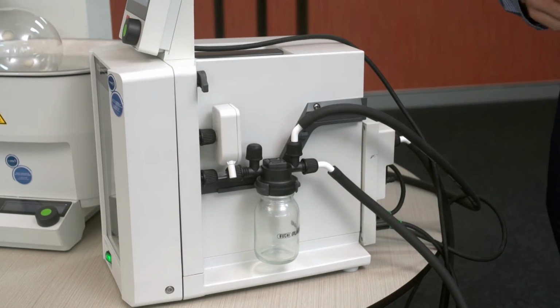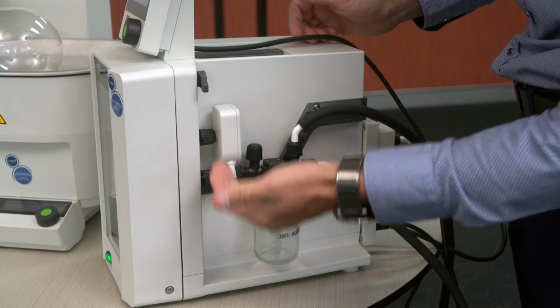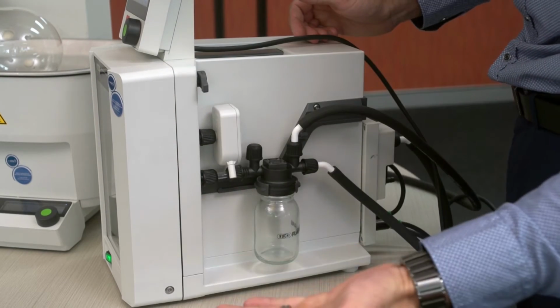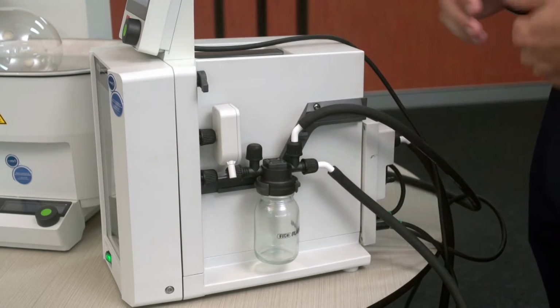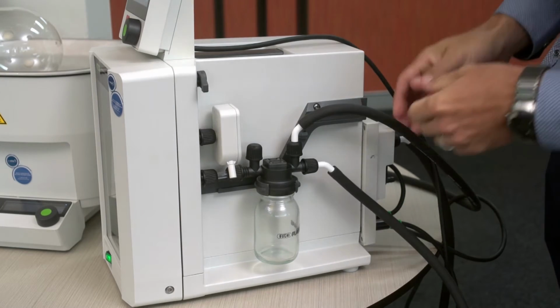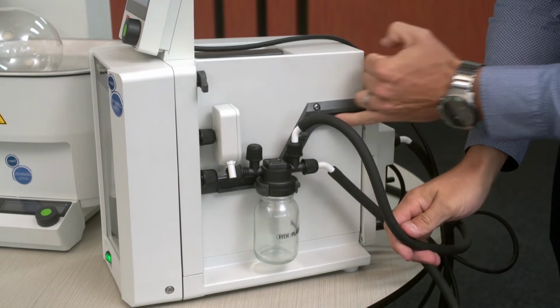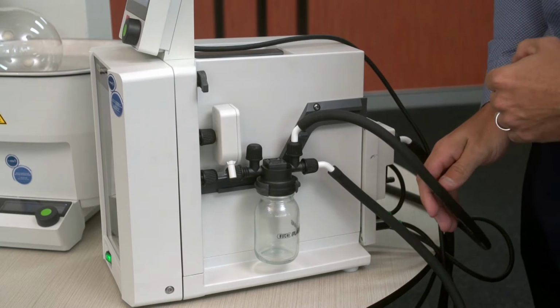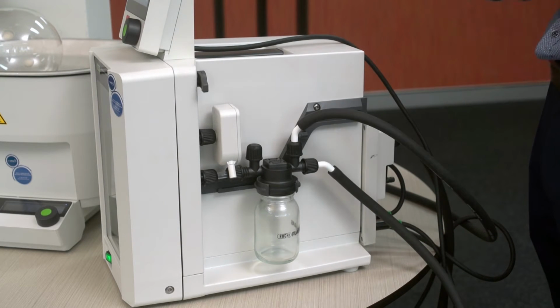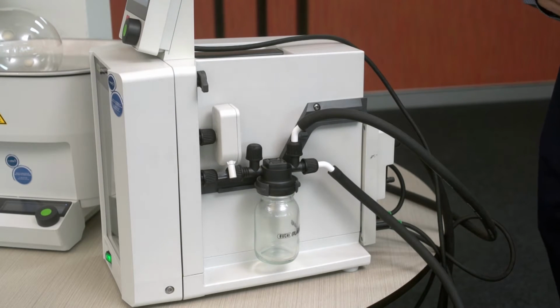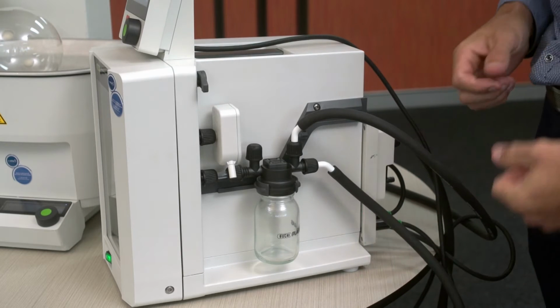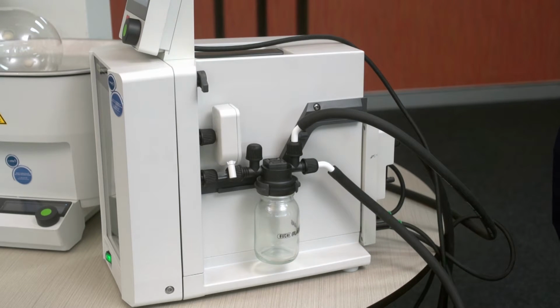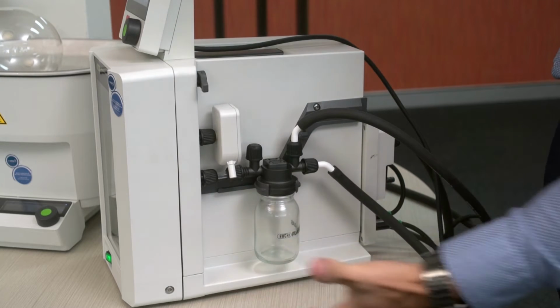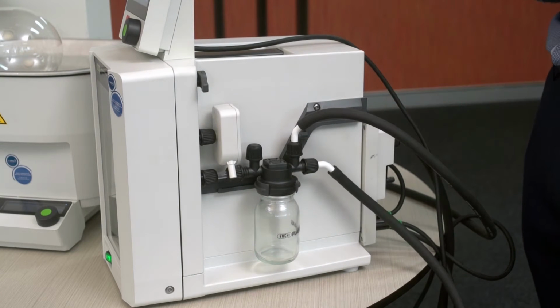Should that happen in future, simply disconnect your inlet and your outlet. Let the pump run and it will air out any condensation that may build up. The pump will be fine. Also on the left-hand side is another groove to fit a secondary condenser. This can be either a vertical, insulated condenser, or a cold trap condenser fitted with a 500ml plastic-coated glass receiving flask. Buchi have designed this to keep everything nice and compact to minimise the footprint on your lab bench.